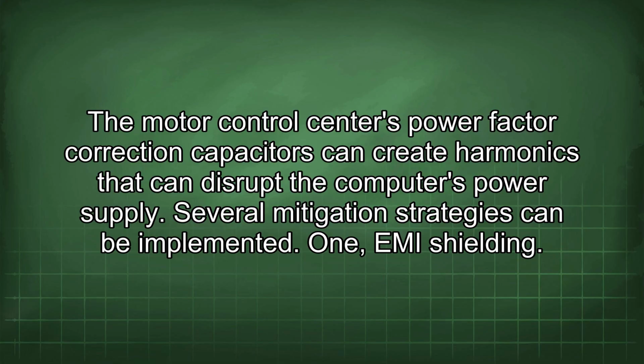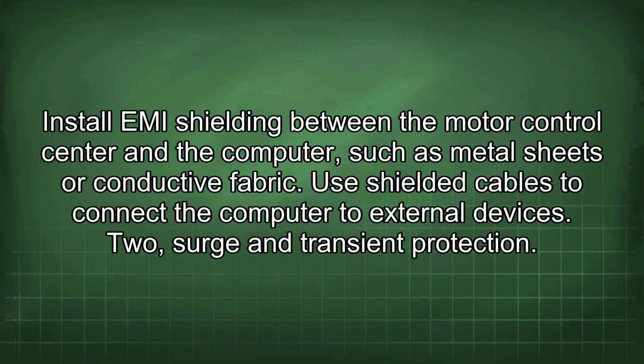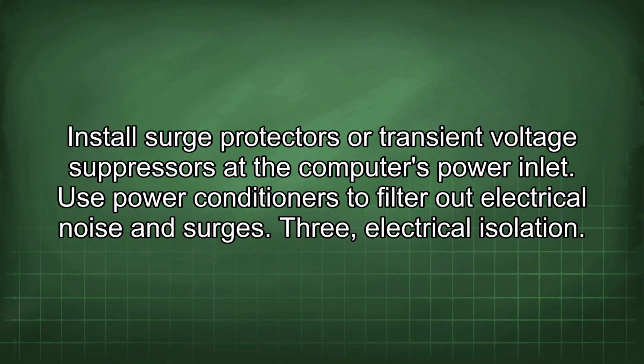Several mitigation strategies can be implemented. 1. EMI shielding. Install EMI shielding between the motor control center and the computer, such as metal sheets or conductive fabric. Use shielded cables to connect the computer to external devices. 2. Surge and transient protection. Install surge protectors or transient voltage suppressors at the computer's power inlet. Use power conditioners to filter out electrical noise and surges.